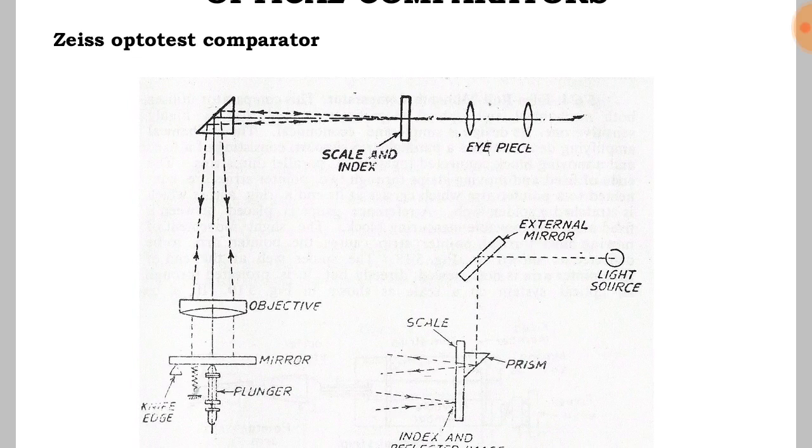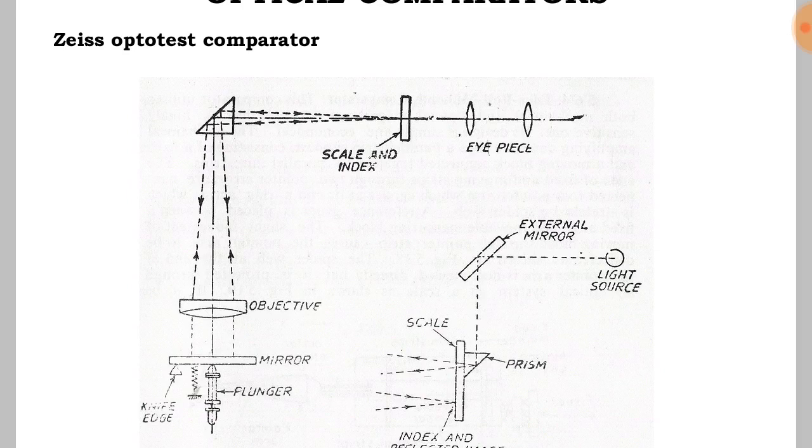This is a commercial measuring instrument. This utilizes a plunger, tilted mirror, objective lens, prism, and observing eyepiece to provide a high degree of magnification. The mirror is mounted on a knife edge and it can be tilted about the fulcrum by any linear vertical movement of the contact plunger.